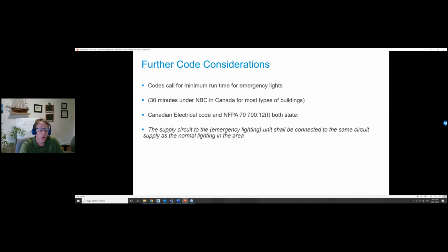One important consideration as you design going forward is this clause, both out of the Canadian Electrical Code and NFPA 70: the supply circuit to the emergency lighting unit shall be connected to the same circuit supply as the normal lighting in the area. What this means is that if the circuit supplying normal lighting in an area goes down, the emergency lighting in that area is supposed to activate. So you can't simply put your emergency lighting systems on an independent circuit and expect to meet the code.